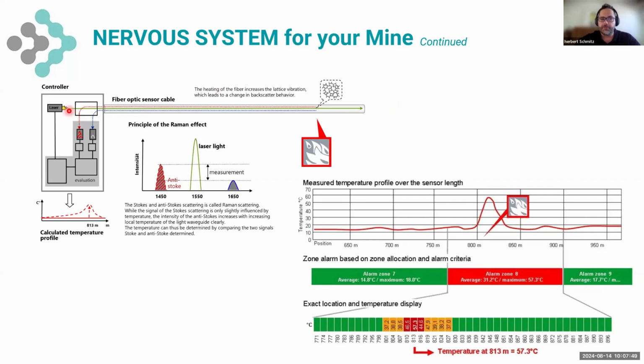Now, the same happens within the silica glass fiber optic core. We heat it, the molecules become more active. We continually shine a laser through the fiber optic cable. This laser light bounces against these active molecules, creating reflection or backscatter. The intensity of the backscatter integrated is our temperature measurement, and the frequency of the light is the distance within the fiber optic cable, think like radar.